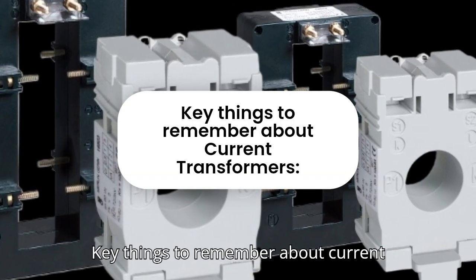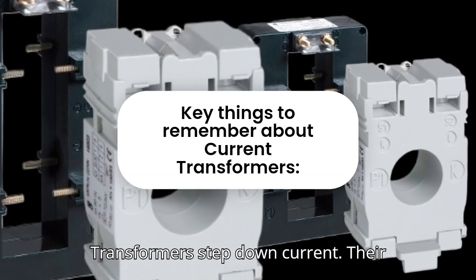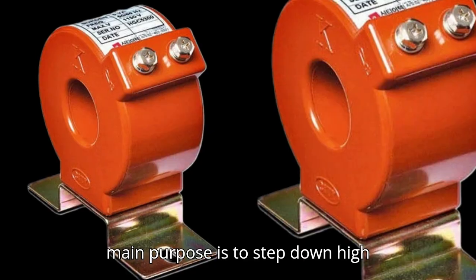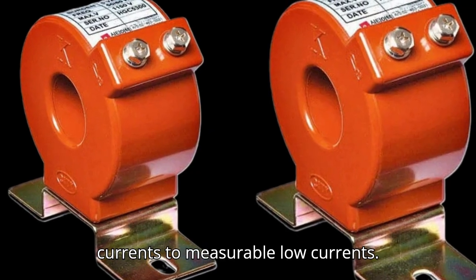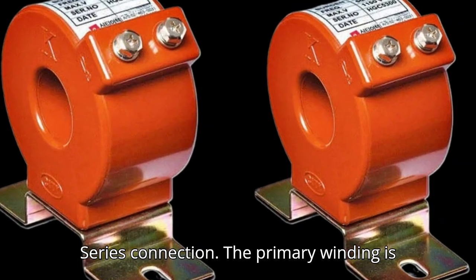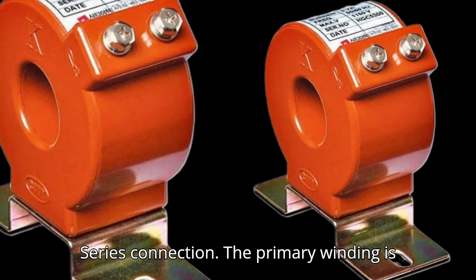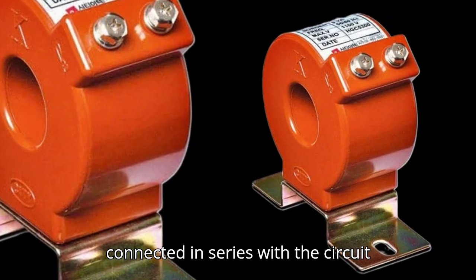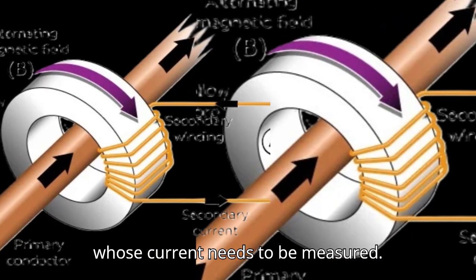Key things to remember about current transformers: their main purpose is to step down high currents to measurable low currents. The primary winding is connected in series with the circuit whose current needs to be measured.